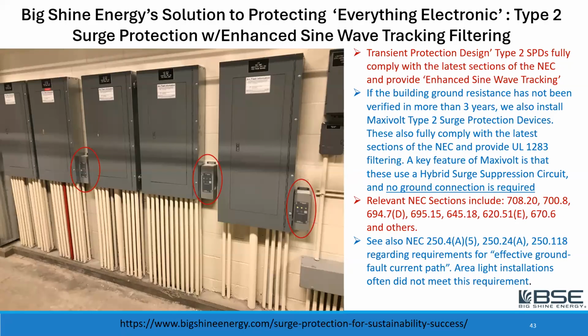What's one of the solutions to all of the issues that we've seen here? Well, one of the things we should do right away, even before we complete our grounding survey or with our grounding survey, is to install type 2 surge protection if we haven't already done so. And we use 2 very excellent companies for our type 2 surge protection. One is Transient Protection Design. They make a surge protector that has what they call enhanced sine wave tracking. Basically, it's a type of filtering that filters out all of that spikiness that you've seen in those waveforms that I showed you. And that's very important because that's what we need to protect electronics.